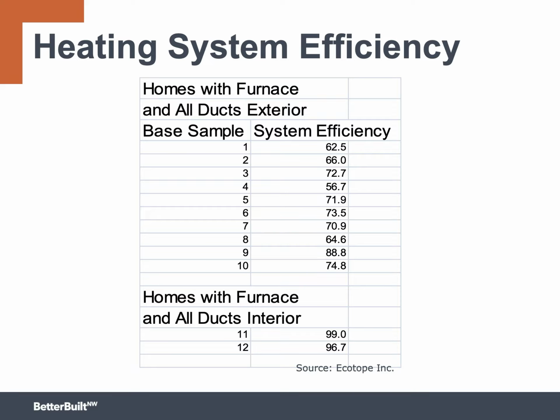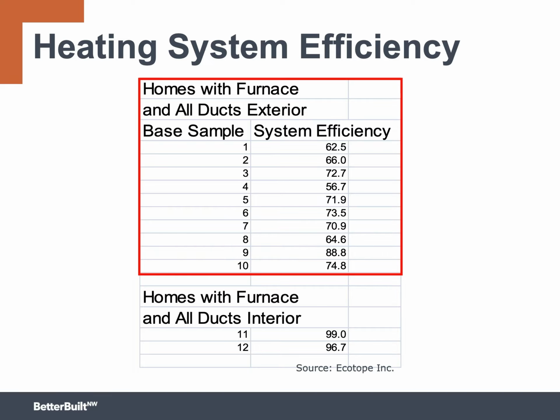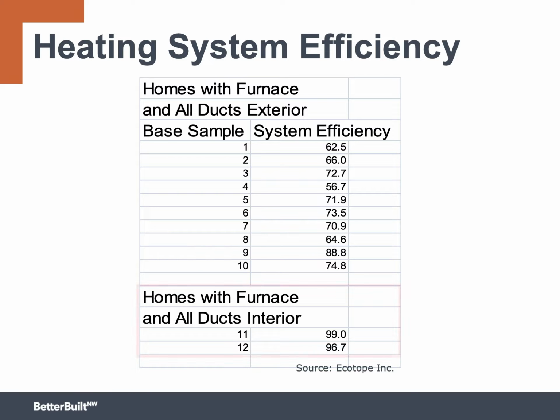Here's work that translates this idea into operating efficiency. This study compares houses with ducts inside versus ducts outside, and you can see the fairly striking difference between them. The table at the top shows the total system efficiency, that's furnace plus ducts, for 10 houses with the ducts in a conventional configuration. If you averaged all those numbers, it's about 70%. That compares with houses with furnaces and ducts on the interior, which is between 97 and 99% system efficiency. There's really a big difference between the efficiency of the systems with ducts inside versus ducts outside.